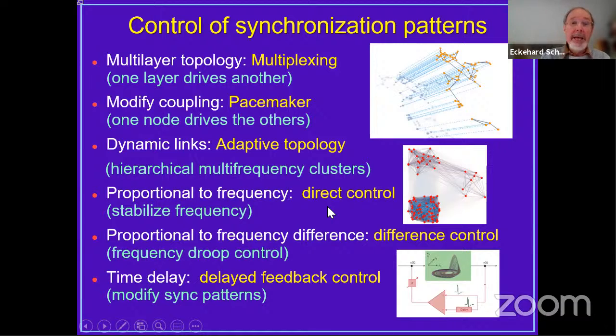More practical kinds of control are, for example, known in the electrical engineering community as direct control, which is proportional to the frequency to stabilize the frequency, or proportional to the frequency difference, which is called frequency droop control. So you have a difference control, or you can use time delay as a means of control.